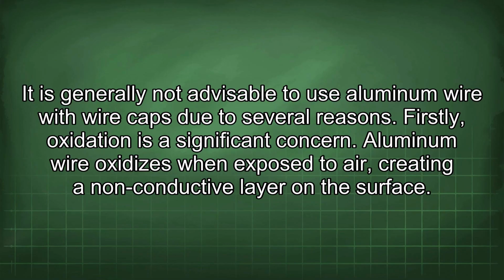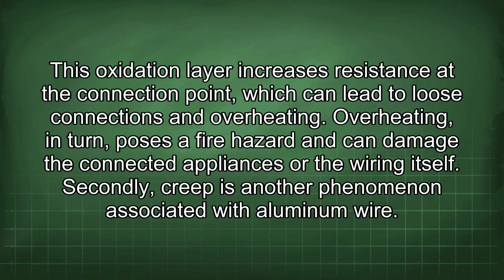It is generally not advisable to use aluminum wire with wire caps due to several reasons. Firstly, oxidation is a significant concern. Aluminum wire oxidizes when exposed to air, creating a non-conductive layer on the surface. This oxidation layer increases resistance at the connection point, which can lead to loose connections and overheating. Overheating, in turn, poses a fire hazard and can damage the connected appliances or the wiring itself.